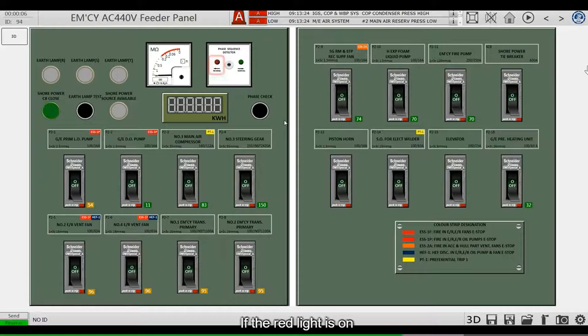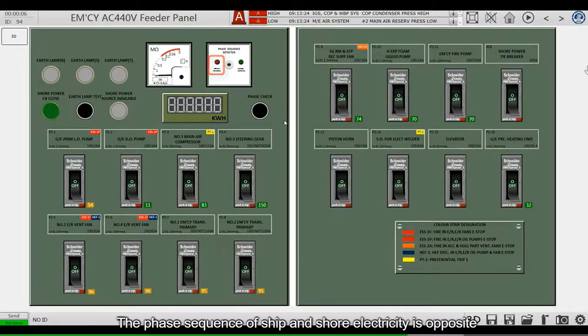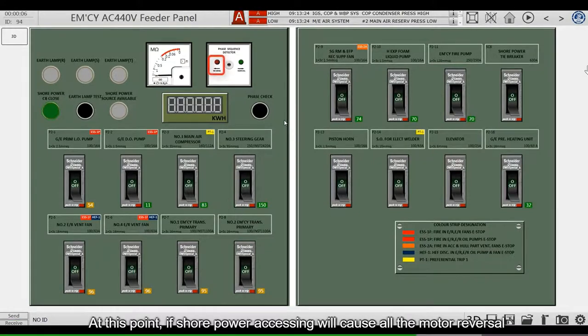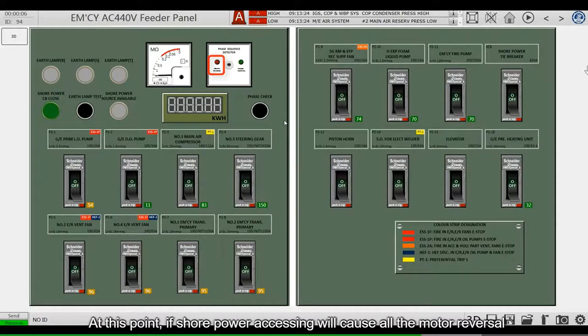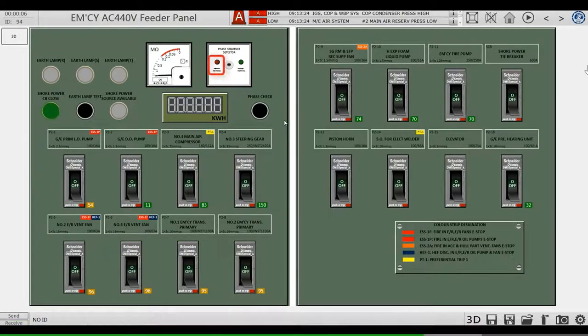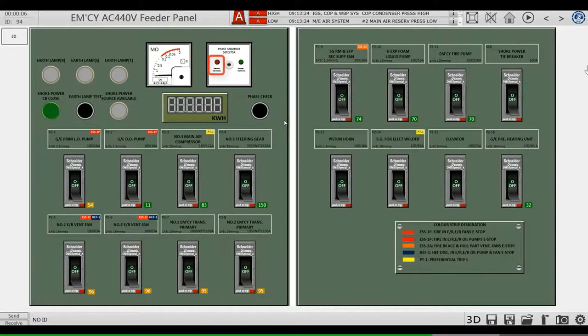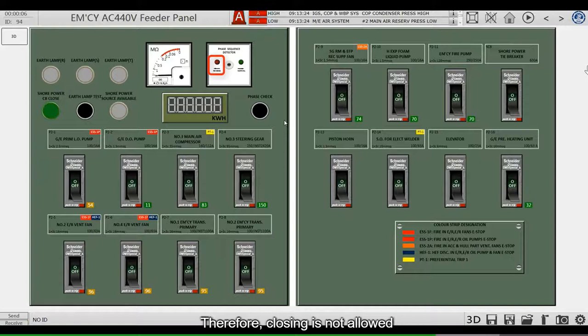If the red light is on, the phase sequence of the ship and shore electricity is opposite. At this point, if shore power accessing will cause all the motor reversal, causing a serious malfunction. Therefore, closing is not allowed.